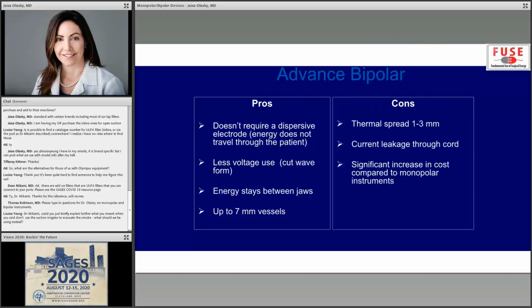You're up to 7 millimeters, and they even have some newer ones that are up to 10 millimeters for the vessel size. So small named vessels, branches of named vessels, things like potentially a lap sigmoid colectomy, not for cancer, where you're on just sigmoidal branches. That's a great time to use an advanced bipolar, where it would be quite tedious to sit there and clip things because they might be too big to take with a monopolar instrument. And at the same time, if you fire a stapler, you're not being nearly as precise. So you have this nice bipolar instrument to use there.